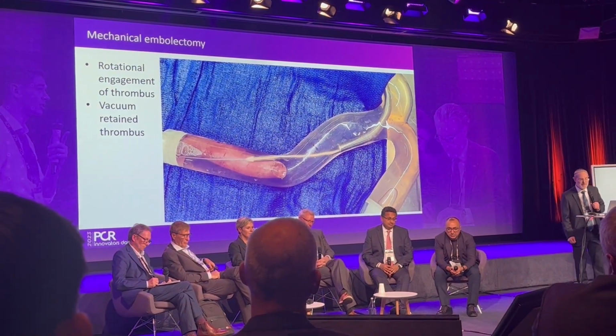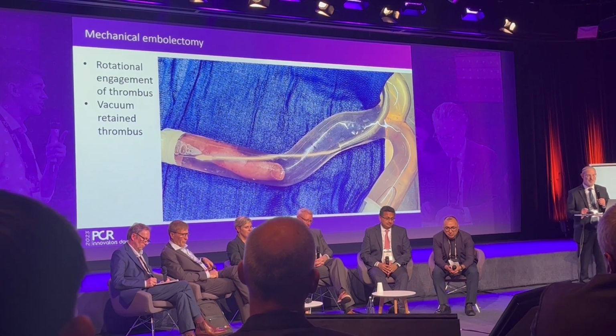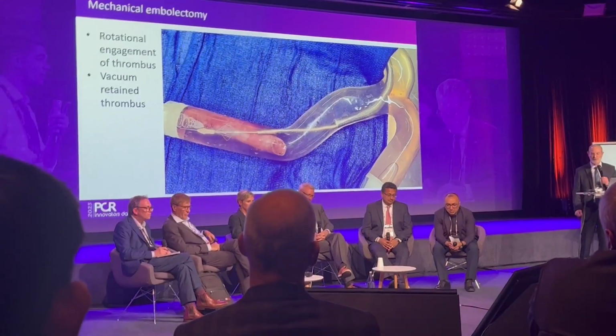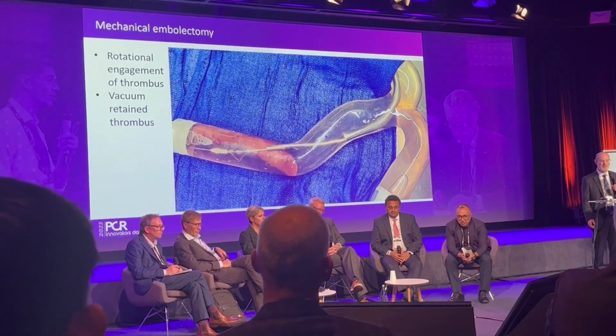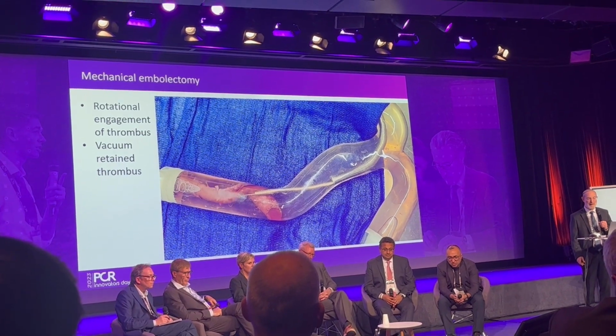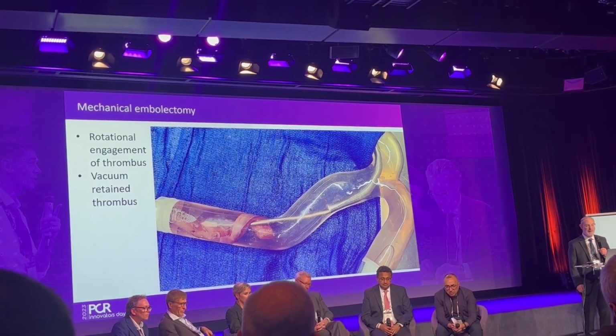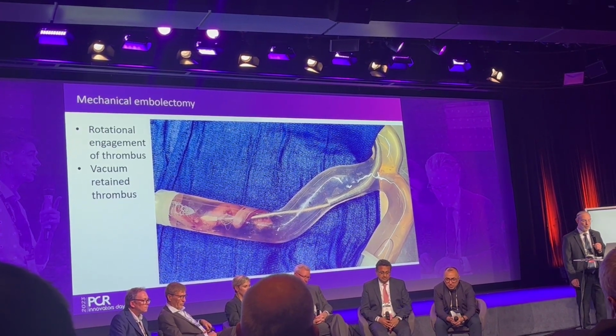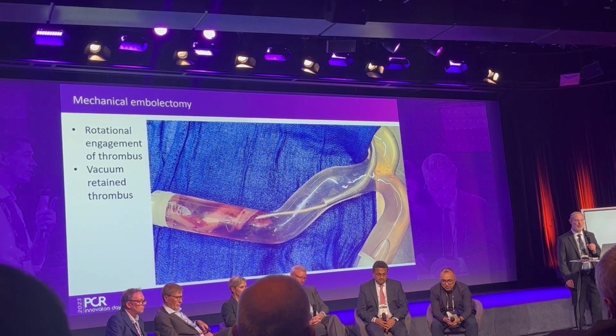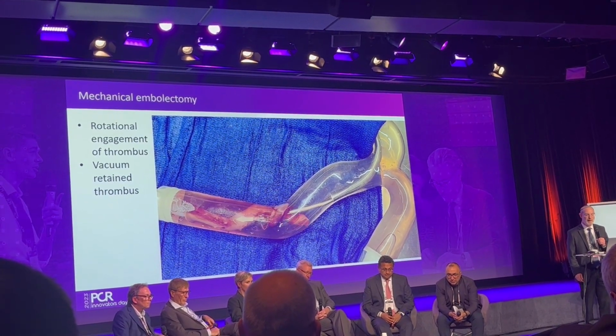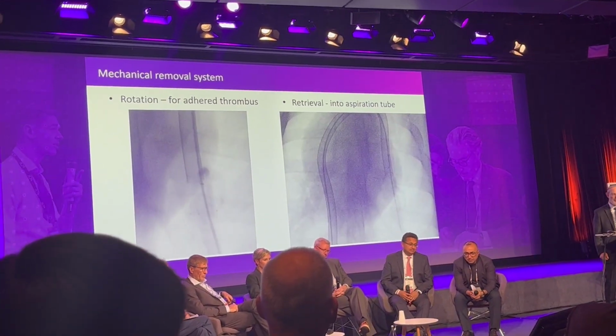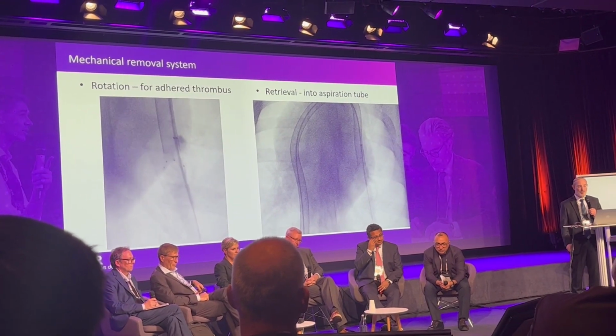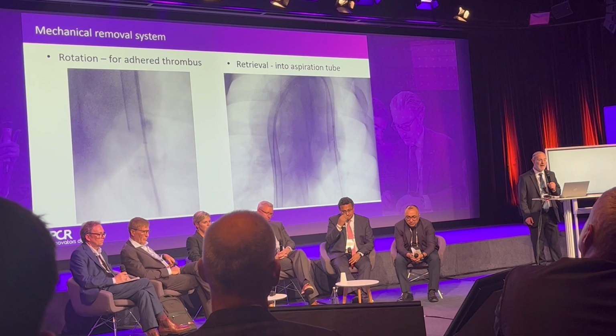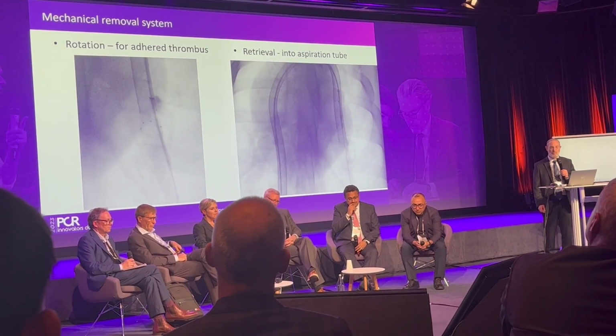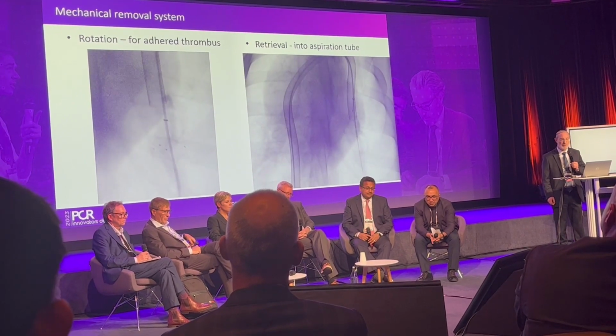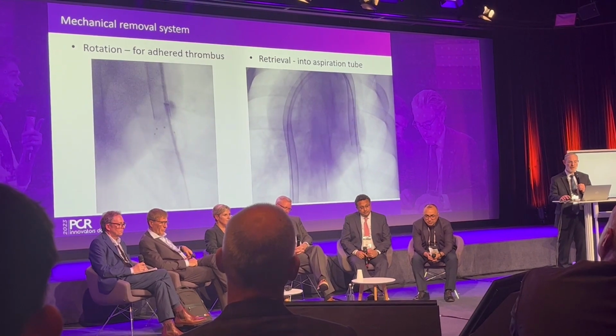the aspiration catheter. This is a model that's a very specific model that uses vacuum retention of the thrombus at the distal portion. You can see the larger aspiration catheter with the distal mechanical system going in, rotates round, entangles and entraps the thrombus, and then is able to retract and pull back towards the aspiration catheter, and you can see it pulling against the vacuum system back at the distal end. In the animal model, we can see each one of those legs of this rotating system has got markers on it. We're able to rotate it into the thrombus and retract it back to that aspiration system, and then move it back through the aspiration system on the right. You can see it engaged into the catheter and retrieved back all at 26 French.